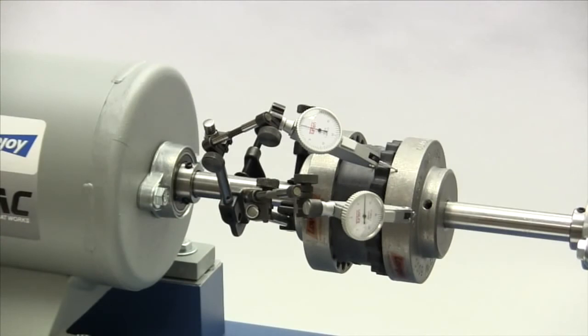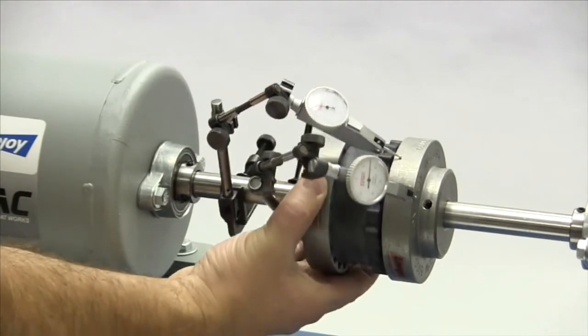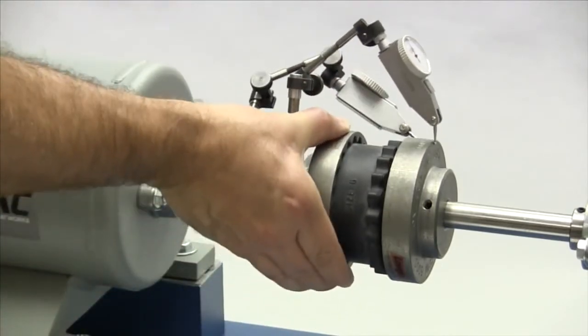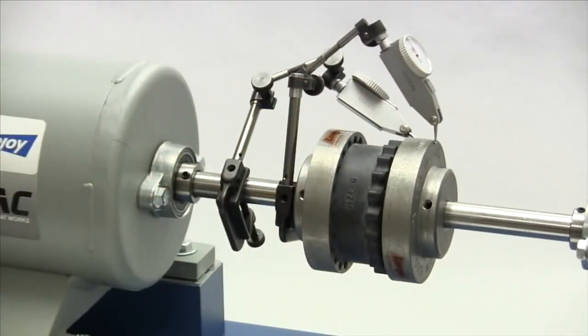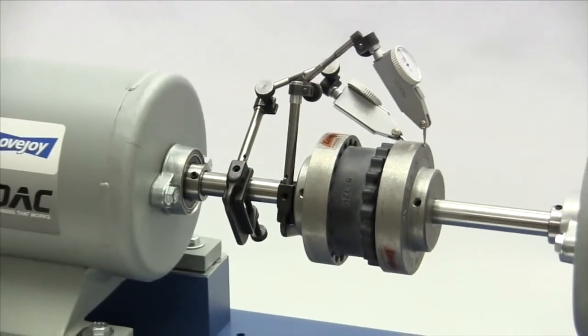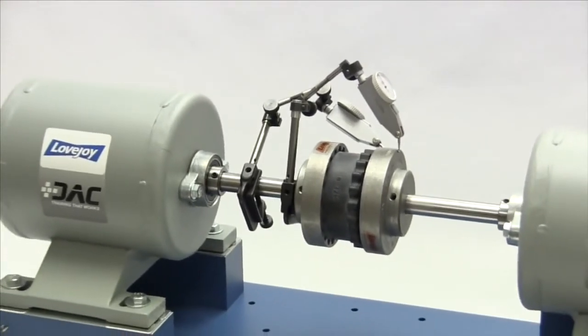If using a dial indicator, mount the indicator on the driver shaft with the sensor touching the flange on the opposite shaft. Rotate the shaft with the indicator to the three o'clock, six o'clock, nine o'clock, and twelve o'clock positions and make notes of the deviation on the dial. If the deviation exceeds the value in the column labeled Angular, adjust the equipment to correct this condition.